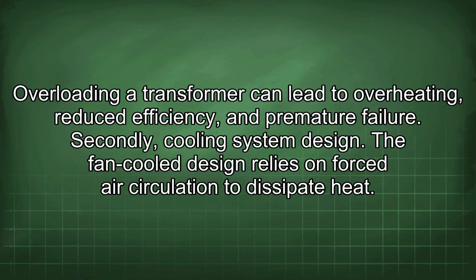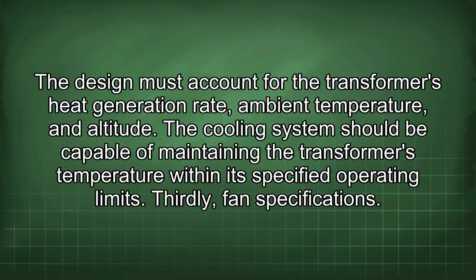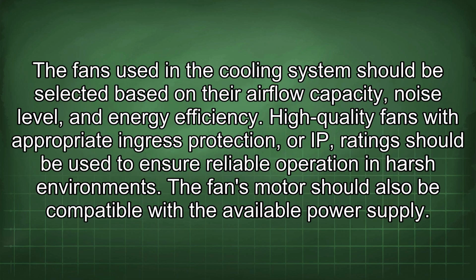Secondly, cooling system design. The fan-cooled design relies on forced air circulation to dissipate heat. The design must account for the transformer's heat generation rate, ambient temperature, and altitude. The cooling system should be capable of maintaining the transformer's temperature within its specified operating limits. Thirdly, fan specifications. The fans used in the cooling system should be selected based on their airflow capacity, noise level, and energy efficiency. High-quality fans with appropriate ingress protection, or IP, ratings should be used to ensure reliable operation in harsh environments. The fan's motor should also be compatible with the available power supply.